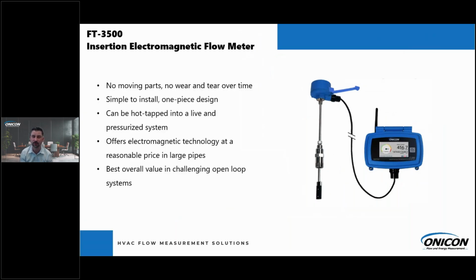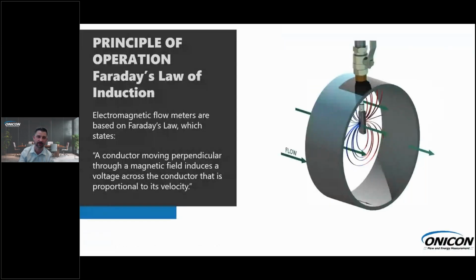So why do we love our insertion meters so much? First off, this meter has no moving parts, so it doesn't matter about the water quality. There's no wear and tear over time, so we're removing the maintenance required over the life of the building. Also, it's a hot tap design, so you can hot tap this into live and pressurized systems. This is great for new construction and for retrofit applications where you can't cut into the system. It's the best overall value for open loop systems. You're getting electromagnetic technology at a great price. It doesn't matter if it's a 2-inch pipe or a 36-inch pipe, you're getting this technology at the same price.